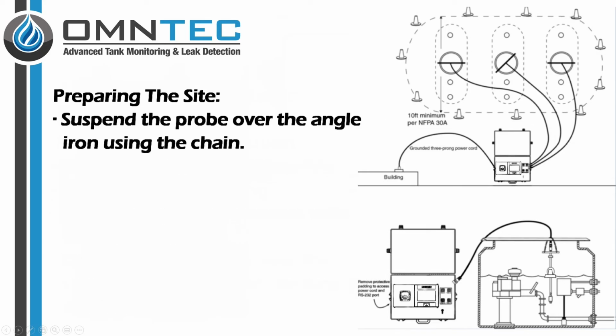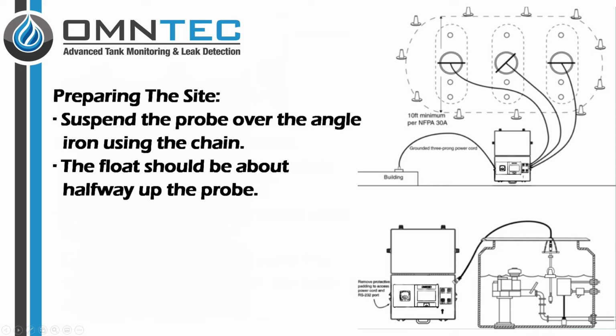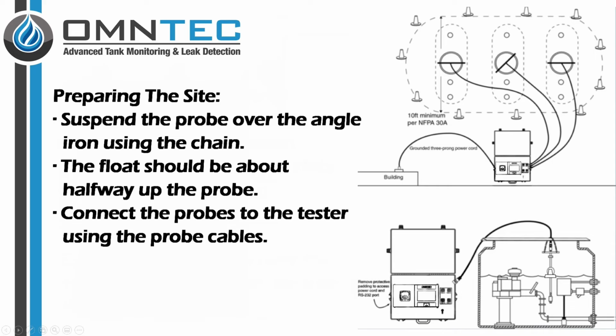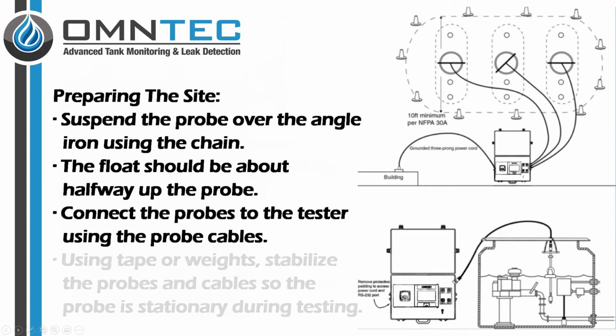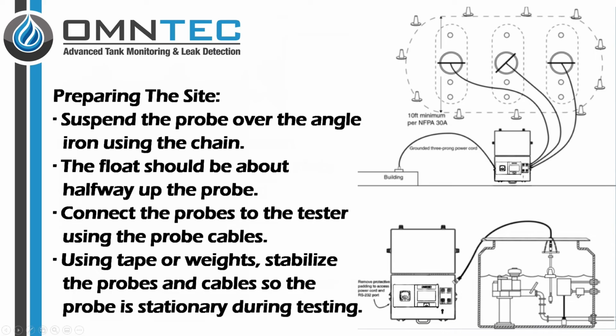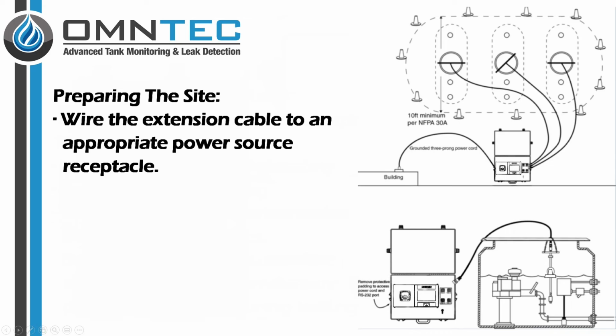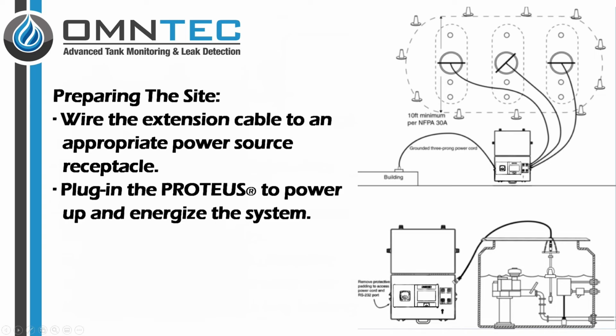Suspend the probe over the angle iron using the chain. The probe should hang vertically, and it should not touch the floor of the containment area. The float should be about halfway up the probe. The float should be free to travel up or down along the length of the probe, with the increase and decrease of liquid without anything hindering it. Connect the probes to the tester using the probe cables. Using tape or weights, stabilize the probes and cables so the probe is stationary during the test. Wire the extension cable to an appropriate power source receptacle. Plug in the Proteus to the extension cable to power up and energize the system.